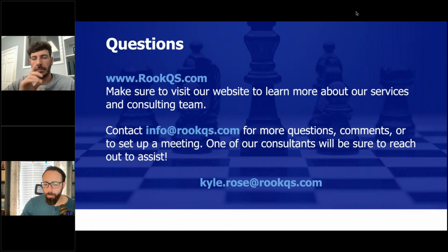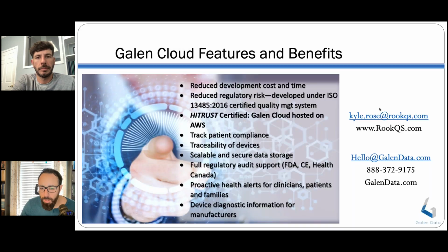Kyle, in terms of questions, we have some that I think are very straightforward, yes or no. So I'll try to ask those first here. One of the first ones is, is it typical that an outside lab tends to do your 60601 testing? Yeah, very, very typical. I think it's very rare that you would do that internally. Okay. Is DHF needed for class 1 devices? And what about QMS for class 1 devices? Yes, for both. Okay.